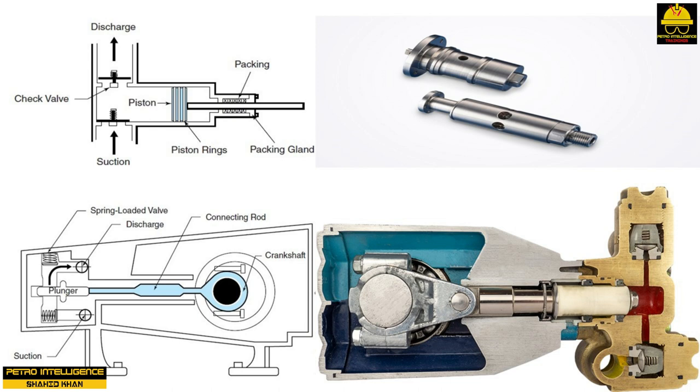The primary difference between a plunger pump and a piston pump is in the shape of the piston or plunger element and the way they seal. A piston pump has rings mounted on the piston that form a seal. The plunger on a plunger pump does not have moving rings. The plunger moves in and out of an O-ring or packing medium to form its own stationary seal.